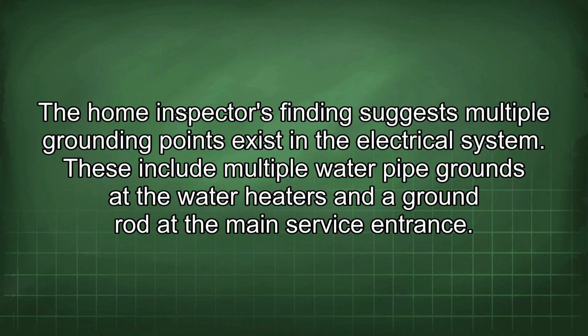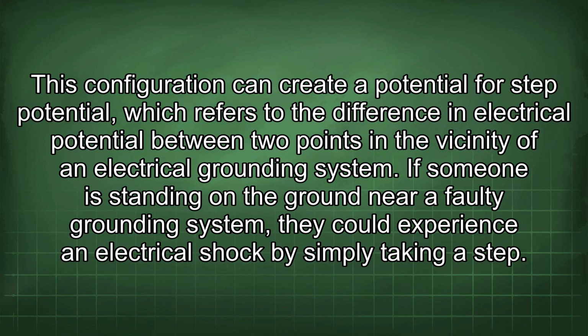The home inspector's findings suggest multiple grounding points exist in the electrical system. These include multiple water pipe grounds at the water heaters and a ground rod at the main service entrance. This configuration can create a potential for step potential, which refers to the difference in electrical potential between 2 points in the vicinity of an electrical grounding system.